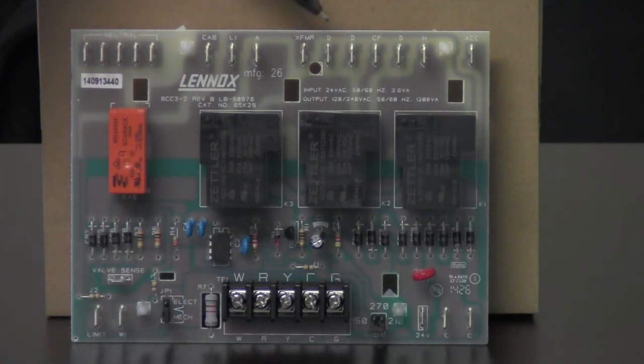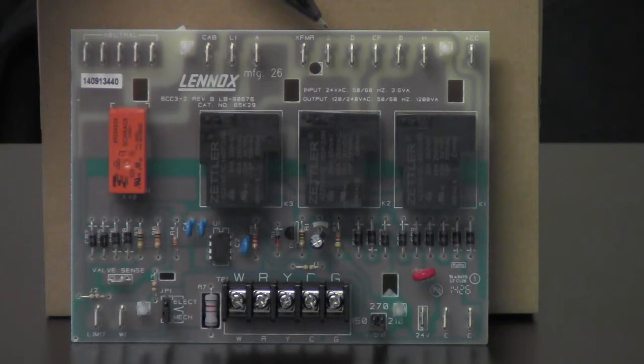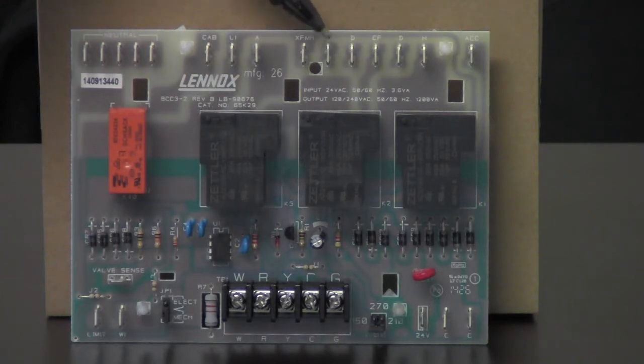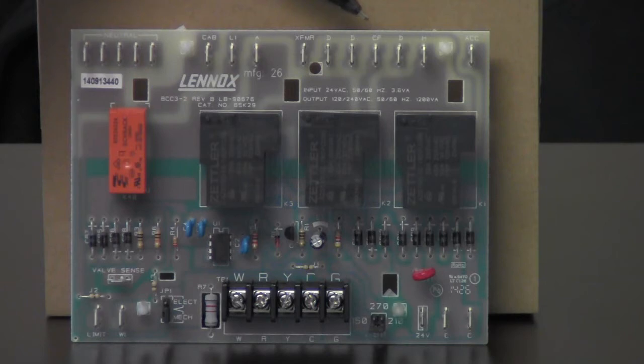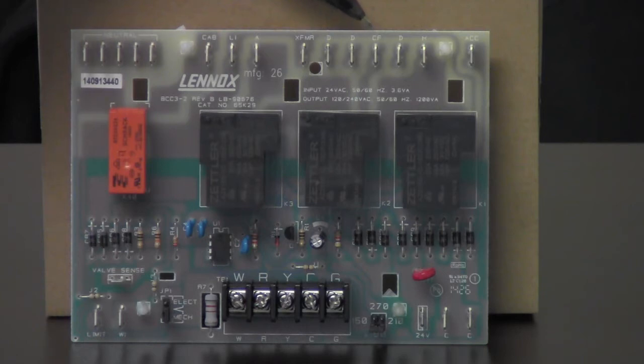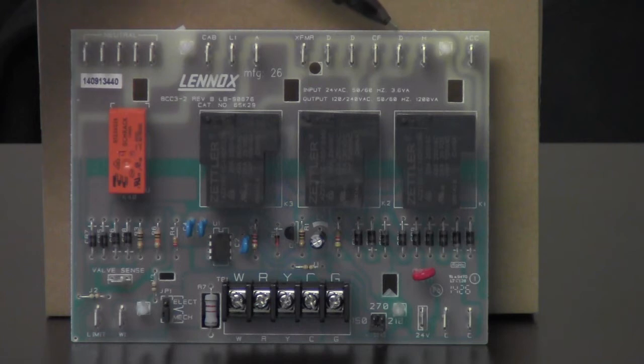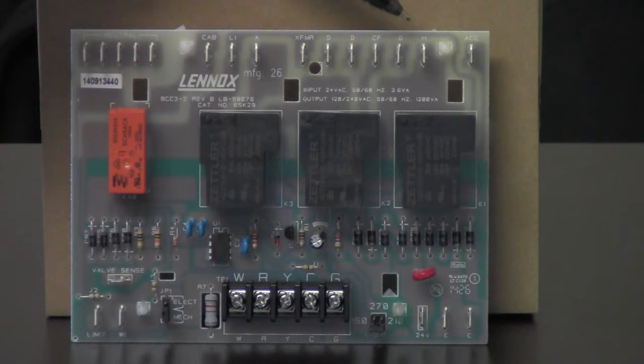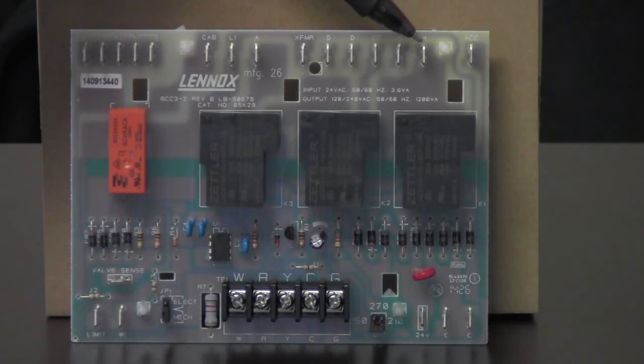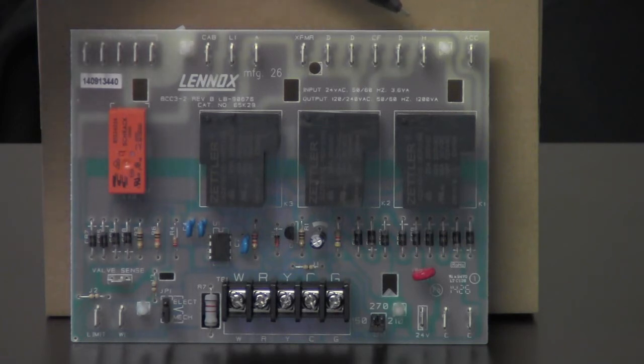Behind this, they don't go anywhere. They're not hooked to any kind of circuitry or anything. They're just there to house those unused blower leads. Next to that we have a CF, that's for continuous fan. Normally we don't need to worry about putting anything on the CF. Next to that we have another D terminal for unused blower leads. Next to that we have an H, that's going to be our heat speed. Usually with heat, you want it to be on low speed. So that's probably going to be a red wire going to our H. That'll put us in a low speed for our heat mode.